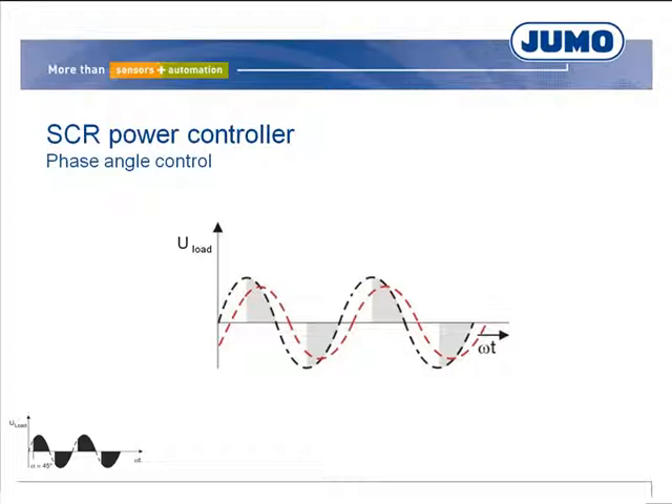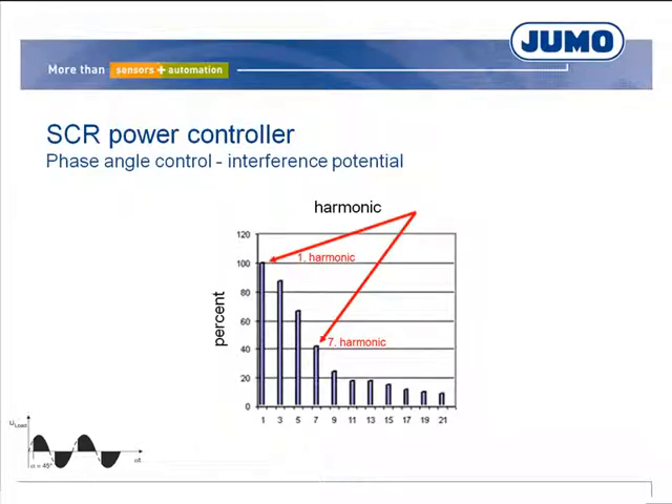In large systems, the reactive power must be eliminated or reduced by compensation facilities. Normally, the fundamental wave is 50 Hz, but due to steep switch-on edges, a multiple of the fundamental wave is also generated. These harmonics have a large interference potential and usually necessitate the use of network filters.